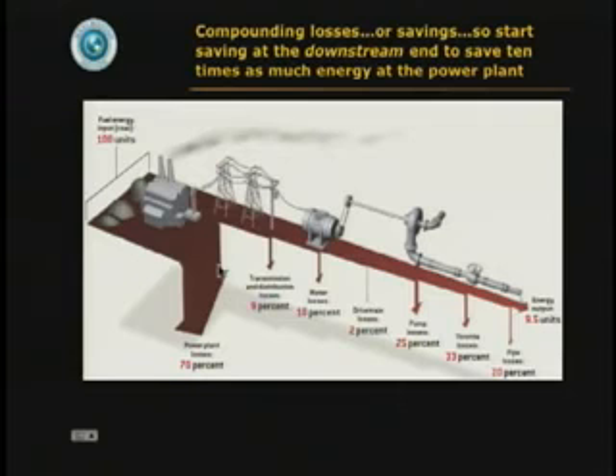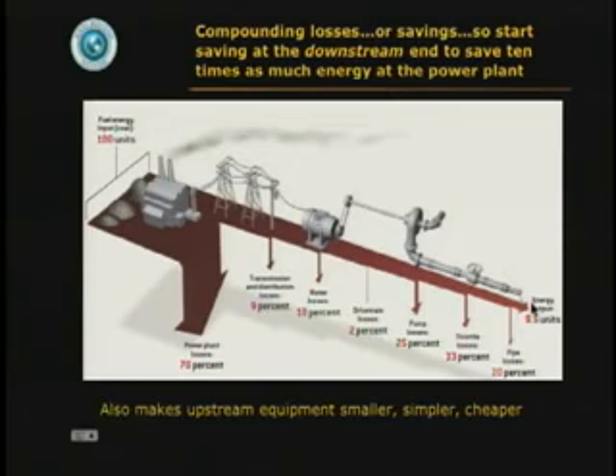Turn that around backwards. Instead of compounding losses going from left to right, think about compounding savings going from right to left. Every unit of flow or friction you save in the pipe is going to save about 10 times that much coal and cost and pollution and global warming back at the power plant. It will also, as you go back upstream, make the equipment smaller, simpler, and cheaper. Saving 1 unit of flow or friction in the pipe saves 2.5 units or so of sizing and therefore roughly capital cost in the motor, for example.